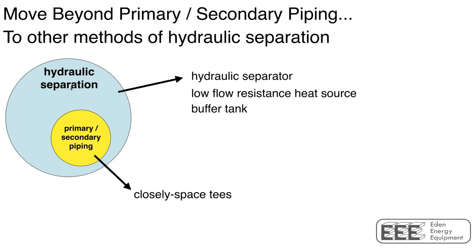Primary-secondary is one way to achieve a desirable effect that we will call hydraulic separation, and it's very simple. Hydraulic separation is whenever you have two or more simultaneously operating circulators, we don't want those circulators to interfere with each other, especially if they're different size circulators. The ideal condition would be each circulator creating a flow rate completely independent of what other circulators are doing in the system. So if circulator number one is operating at 10 gallons a minute and we turn on another circulator, that flow doesn't change at all, and vice versa.